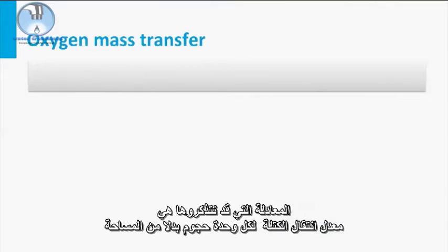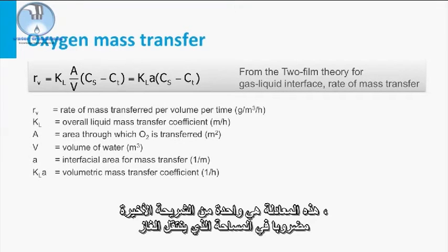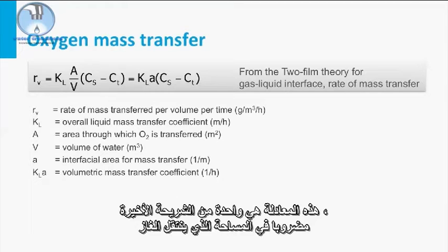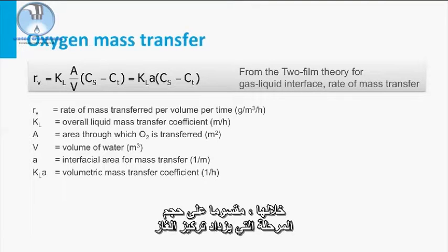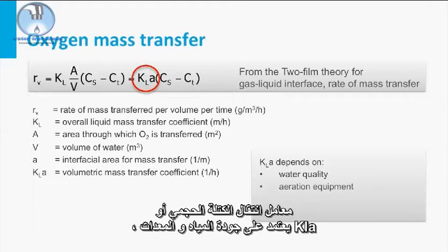An equation you might recognize is the mass transfer rate per volume instead of area. This equation is the one from the last slide multiplied by the area over which gas transfer takes place, divided by the volume of the phase in which the gas concentration increases — in our case, the water volume. The volumetric mass transfer coefficient, or KLA, depends on the water quality and the equipment.